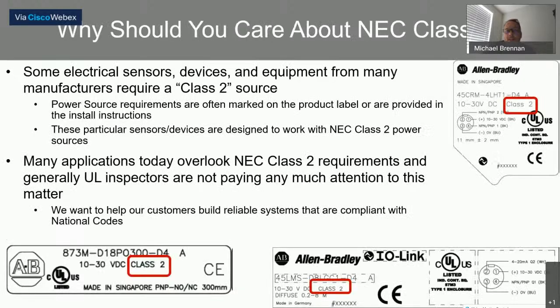So how do I determine if I need a Class 2 circuit? Here's an example of 3 sensors that exist today. Some of them are laser measurement, some of them are color measurement, but you'll note specifically on the side of the sensor the requirement for a Class 2 source. We're seeing this more and more as our sensors become more complex and offer more and more features, that there is the NEC requirement for them. Now, these sensors are specific to Allen Bradley, but all manufacturers that we're seeing across the board for their high-end sensors are beginning to require Class 2 sources.